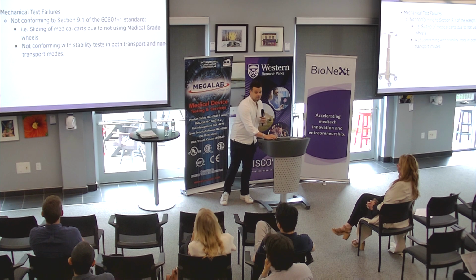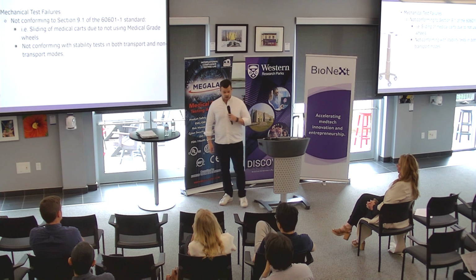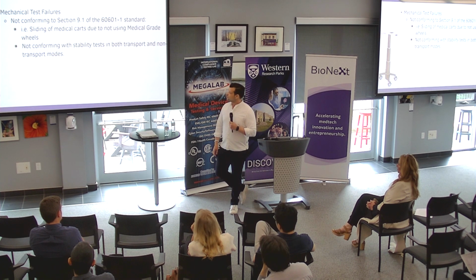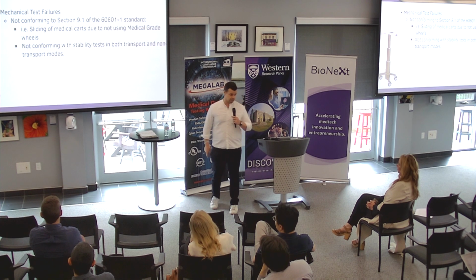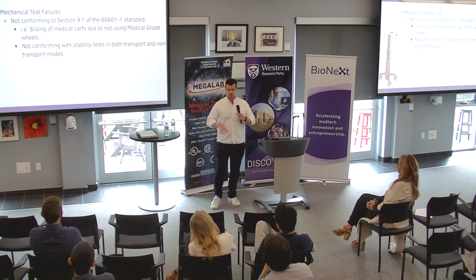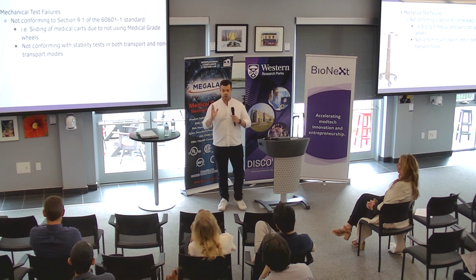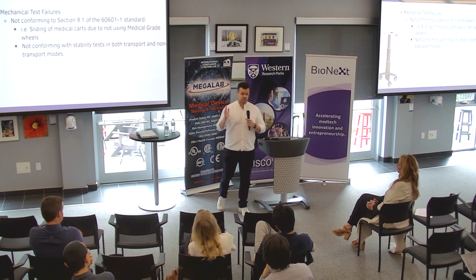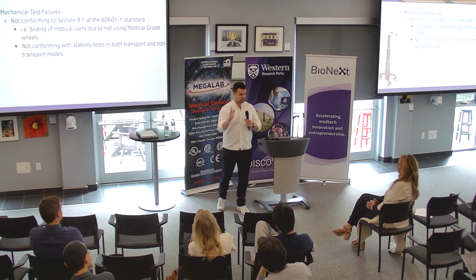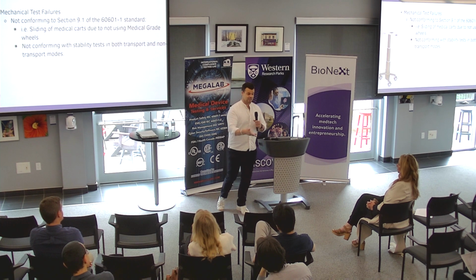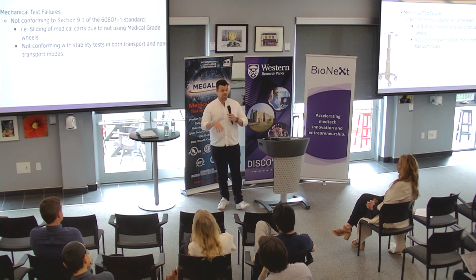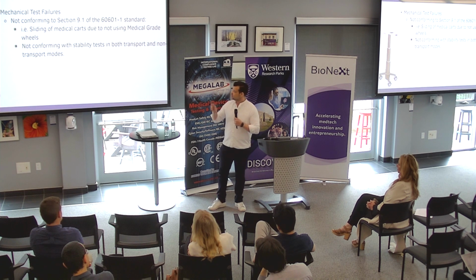Something real simple. Let's say you're making a medical cart. This has happened a couple times. The bottom one there is a stability test. So you actually have to have a certain width of the legs, and you have to pass a tip test. I don't remember what degree it's at, but if you tip it over just a little bit and it falls and crashes, it's a fail. So you have to have a wide base, and there are actually medical grade bases. Also, it says there are medical grade wheels as well.